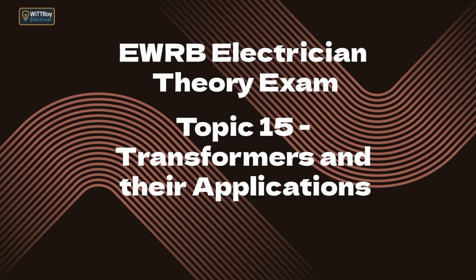In a star-delta transformer, the primary is star and the secondary delta, often used for certain industrial loads. In a delta-star transformer, the primary is delta and the secondary provides a neutral point, common for distribution networks. In a delta-delta configuration, both windings are delta, useful where no neutral is required. Each connection changes line and phase voltage relationships and is chosen based on the application.